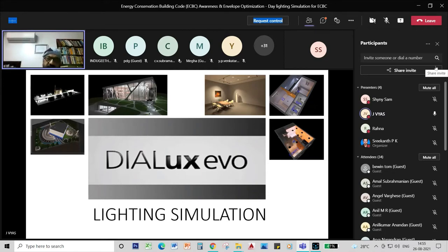and I've got a demonstration board featuring my car that should have 750 lux, and I've got an office area where people can discuss the bank loan or something like that, that should have 300 lux, and one coffee lounge where people can wait for their relatives should not have more than 50 lux, so that people can get relaxed at that place. So 50 lux, 300 lux, 750 lux, and 3000 lux are requirements for a single showroom. Four different types of requirements are there.